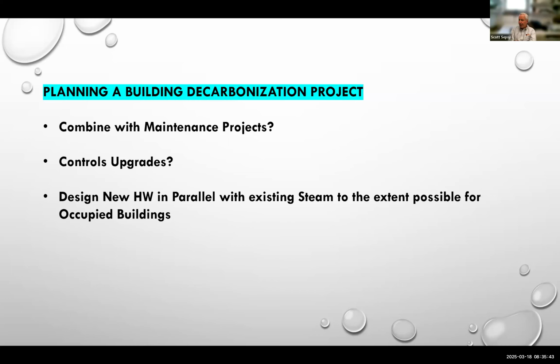Design building systems in parallel where you can. For occupied buildings, if there's room to build in parallel, a new hot water system being installed with the existing steam still active, as you saw on that one slide a few back, then you can minimize the shutdown windows and perhaps retreat if something goes sideways in your project, like a busted schedule. In my experience, this is really an essential part for occupied buildings.